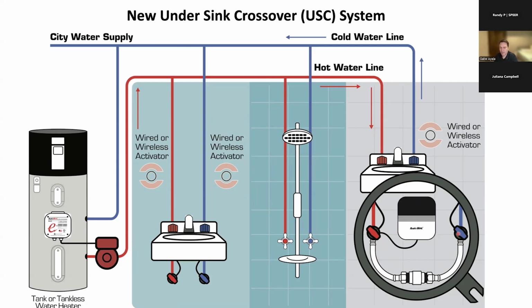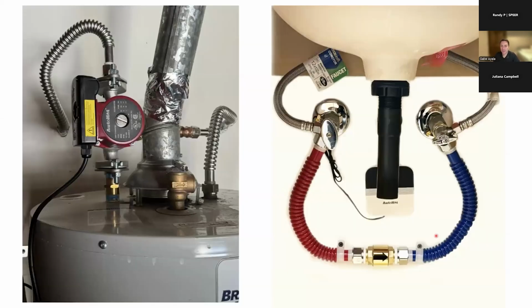It's a very easy way to get on-demand recirculation without having to do any extra repiping or plumbing. You don't need to have power underneath your sink because this little wireless temperature sensor is battery operated. The previous version of this type of equipment required that the pump be installed underneath the sink because the pump had to be told to turn off based on that 6 degree delta. But now that we have the pump back at the water heater, you no longer need the power underneath the sink. So this is all done by battery.